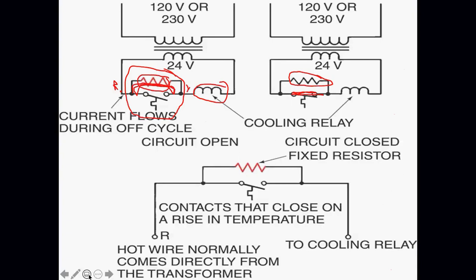If you look at this first circuit, let me erase my scribble so you can see it. When the thermostat is not calling for cooling, where's my power going? I have two loads in series, right? In this first diagram I have two loads in series when my thermostat is not calling. This resistor is at a resistance where it's going to take all of the power. The coil is just being used as a path back to neutral. Remember I told you there's only a couple of occasions in the HVAC industry where we have loads in series. This is one of them, the cooling anticipator. When the thermostat is not calling, this cooling anticipator is in series with the coil.